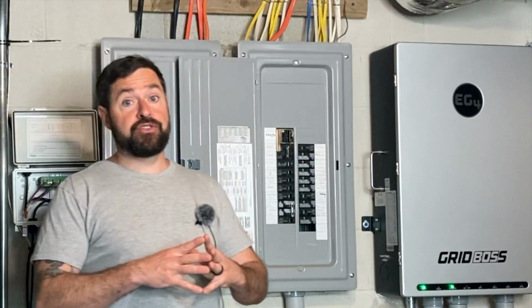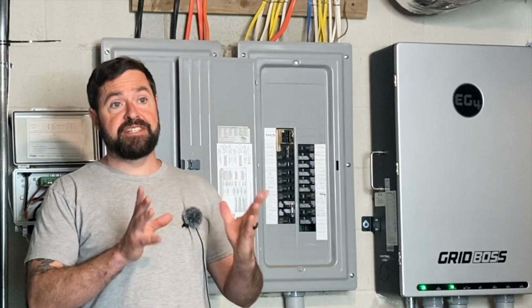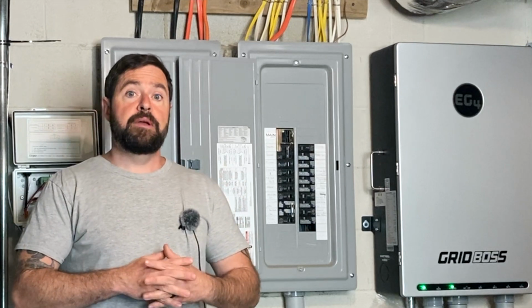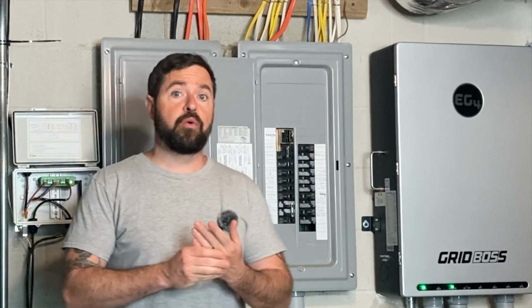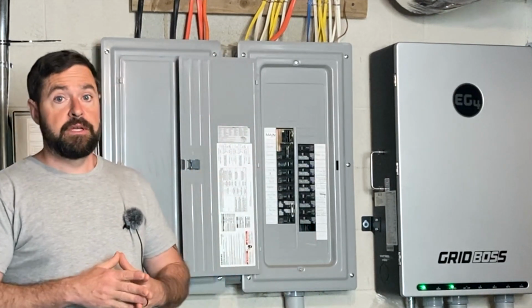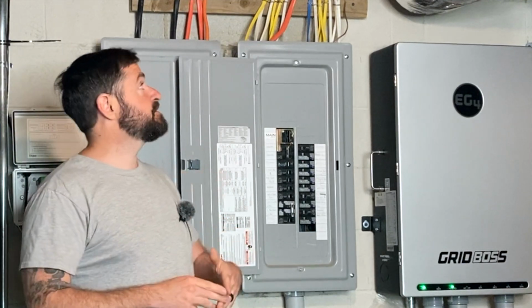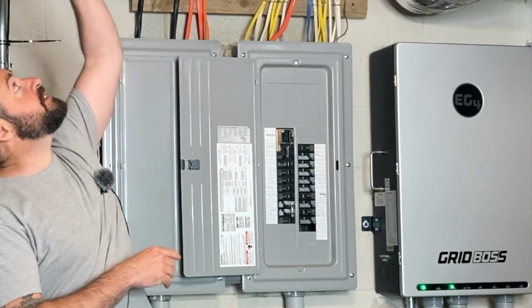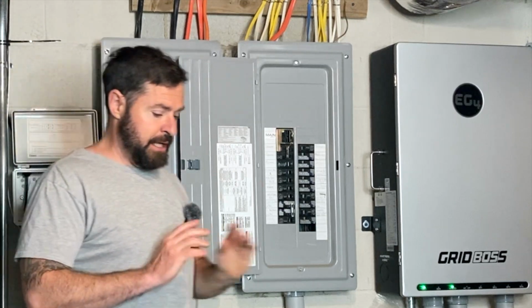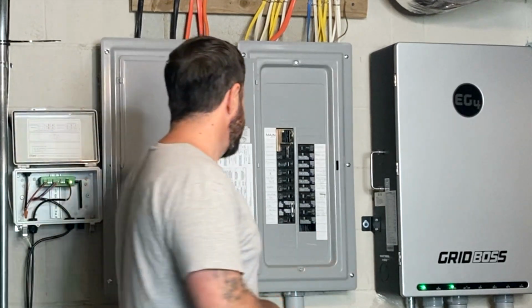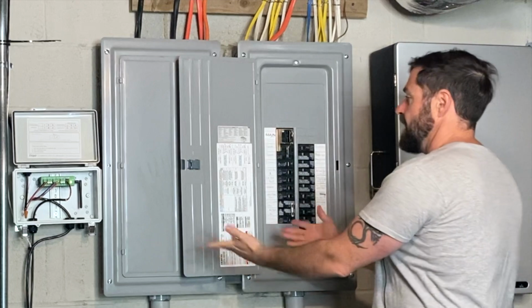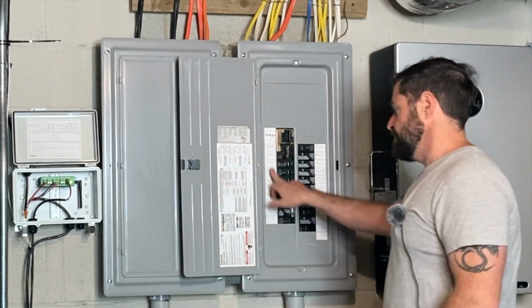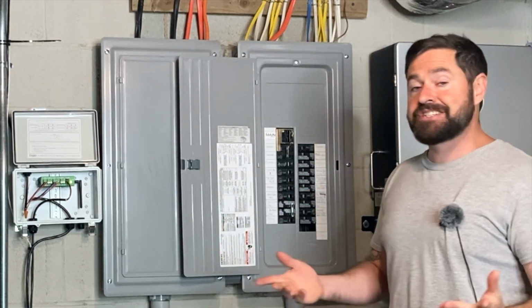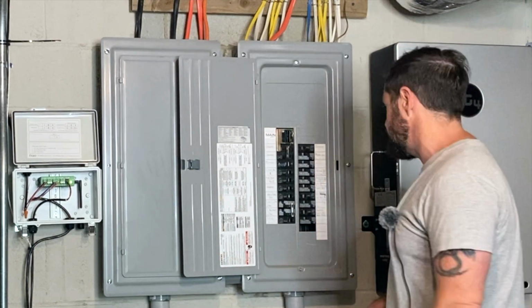Next, you're going to want to make sure all of your holes into the home are sealed up with either caulk or some duct seal. You're going to want to do all the little stuff, clip all these little zip ties, and make it look nice and clean. You're going to want to make sure all of your breakers are labeled. That sounds small, but you're going to fail an inspection every time if you're not labeling your breakers.